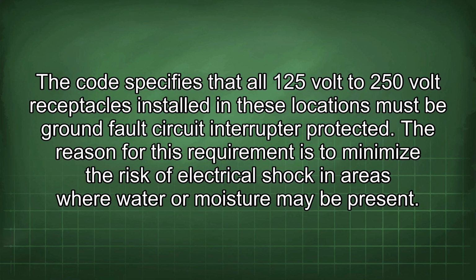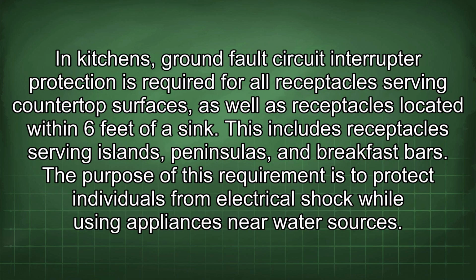In kitchens, ground fault circuit interrupter protection is required for all receptacles serving countertop surfaces, as well as receptacles located within 6 feet of a sink. This includes receptacles serving islands, peninsulas, and breakfast bars. The purpose of this requirement is to protect individuals from electrical shock while using appliances near water sources.